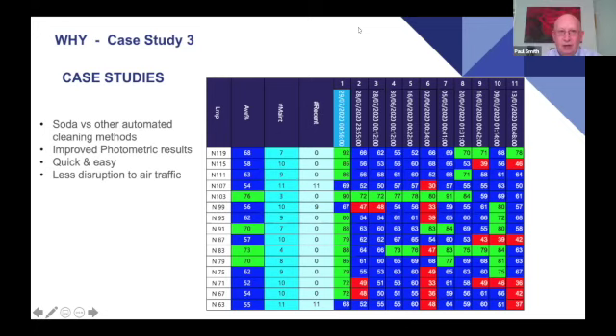We have seen occurrences where customers of ours have said, oh yes, lamp XYZ, that one always fails. We know that because when we go to have a look at it, it's tilted, it's moved. What we've got to do is some civils work before we can do anything else. So they know their airfield, they get to learn their airfield and where these problems are by looking at regular photometric inspections. So it is recommended that you do them on a regular basis and not just do the maintenance once a year, as Robert said earlier.